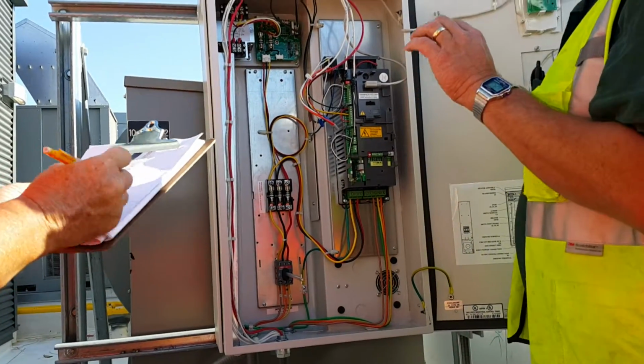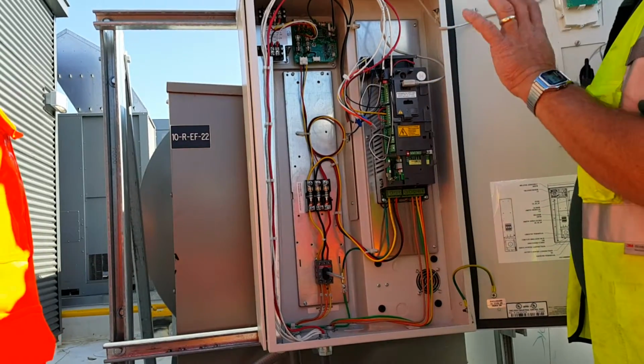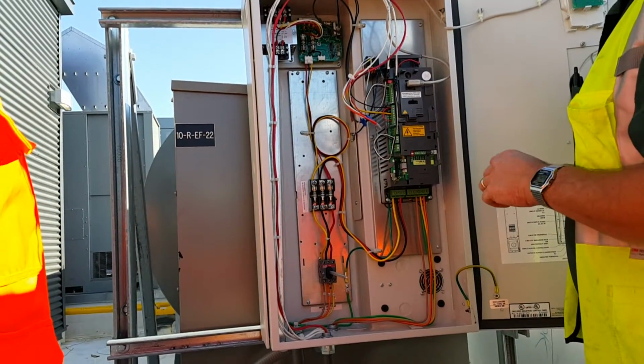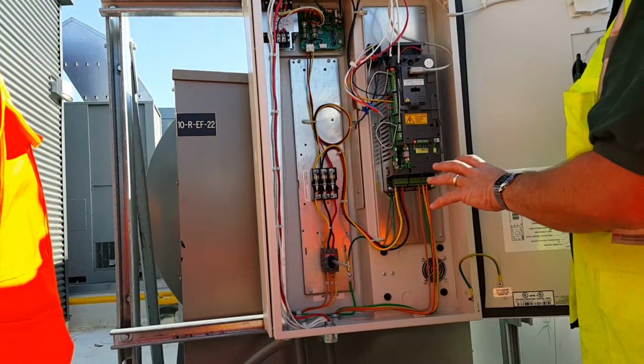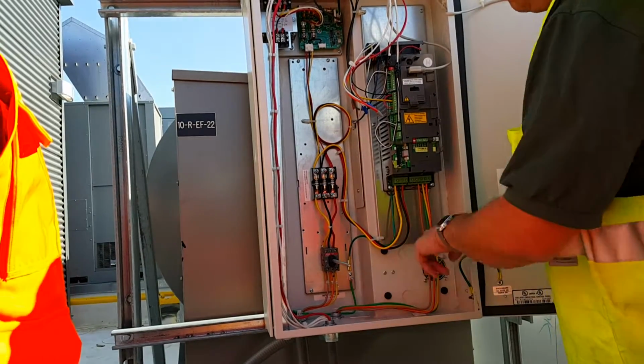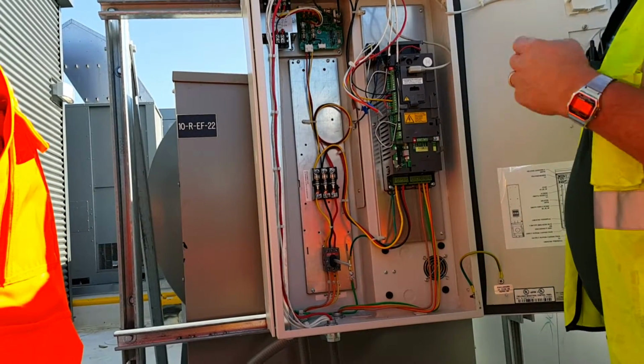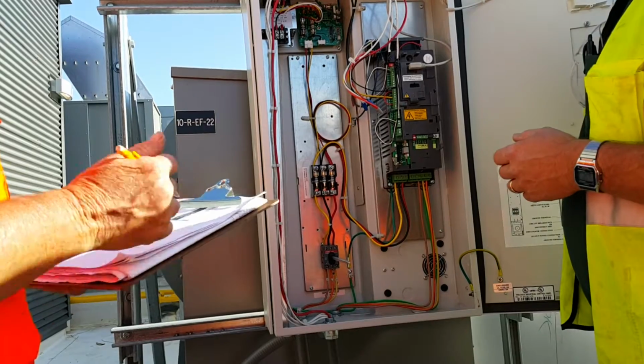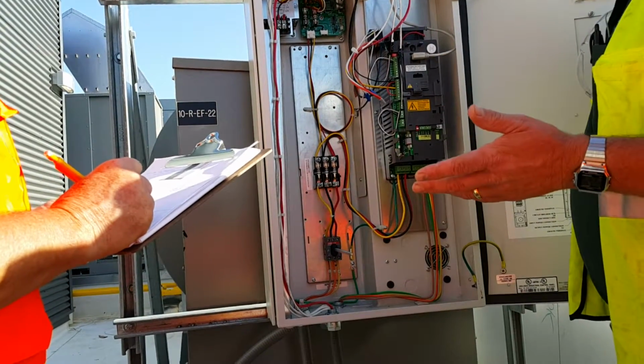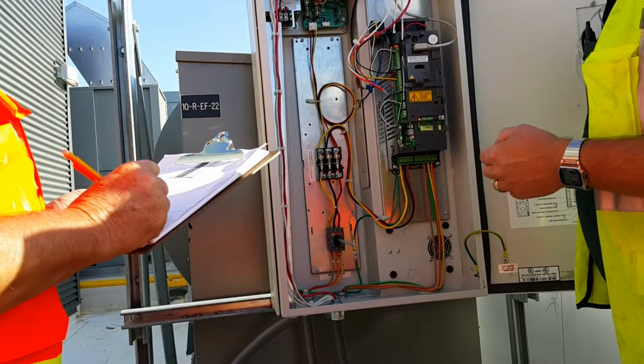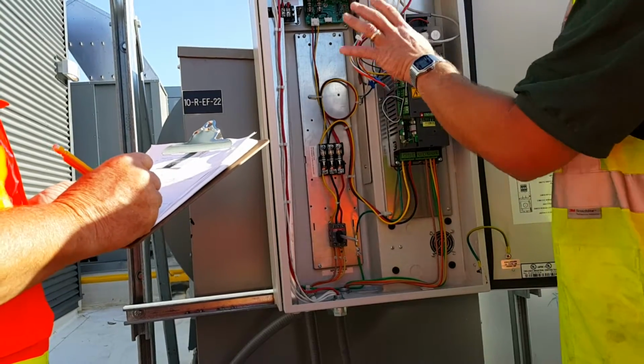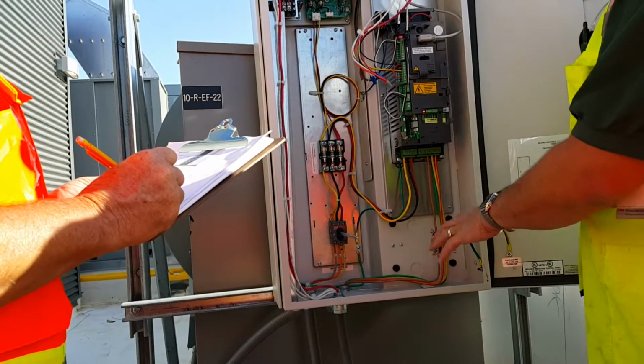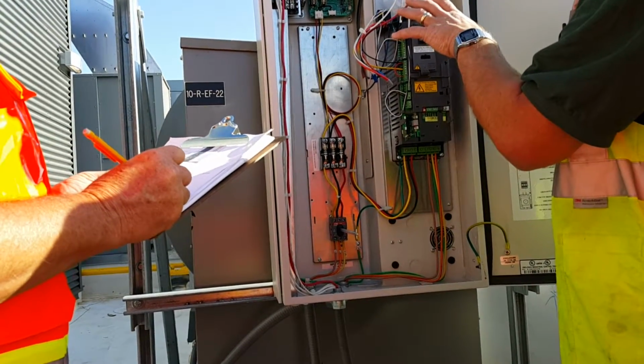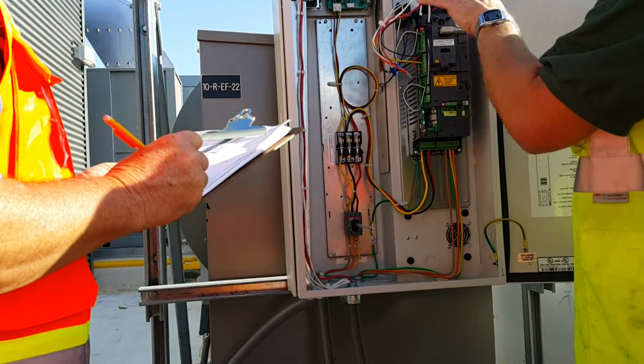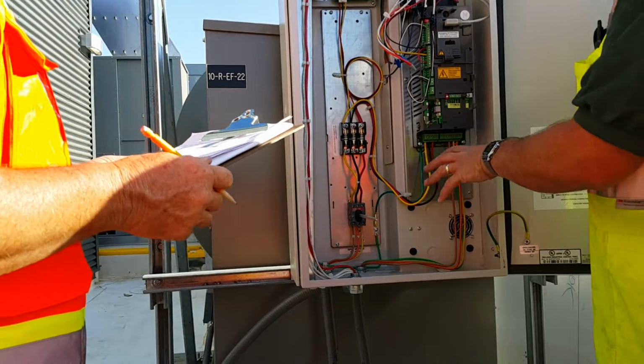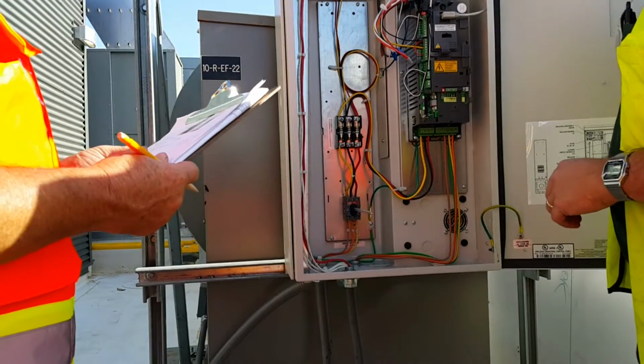But ABB's got a really good torque spec where everything's really, really good on there, and they've already also been burned in. But as far as the field connections, it's always a good idea, once they've got to expand and contract a few times, to do that, and then check that once a year. Give a good visual inspection. Make sure nothing's looking overly dirty, especially on these outdoor units, and make sure that you don't see any heating going on, like in the wiring and those types of things.